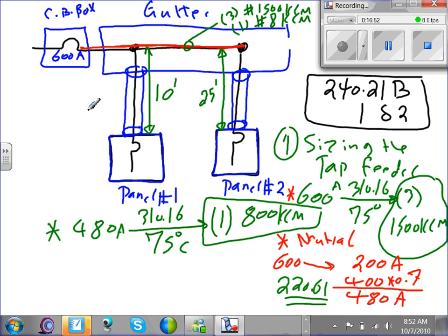Any question? So we size the feeder. As long as we're on sizing the feeder, my friends, let's just complete the sizing since you guys are designers and engineers. We have a neutral and 3 phases. What other conductor do I need? A grounding conductor, assuming there's a PVC conduit coming here. Let's go size the equipment grounding conductor as long as we're on it. Everything I've done so far is still for the feeder.